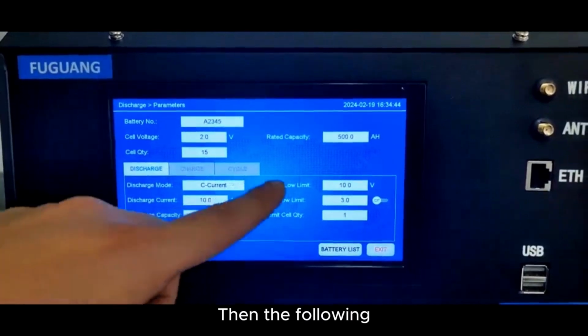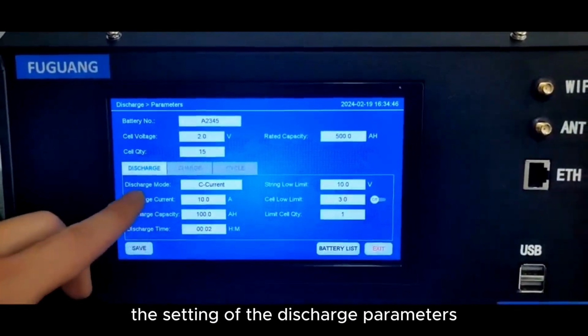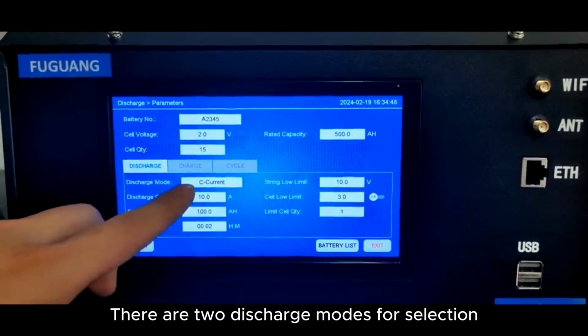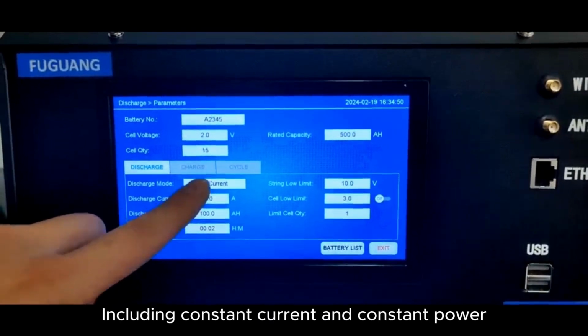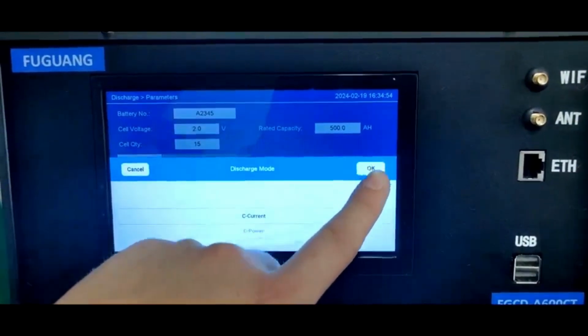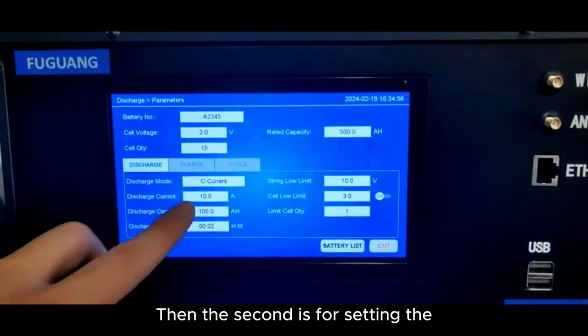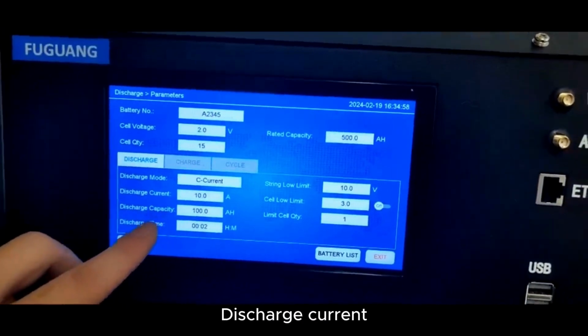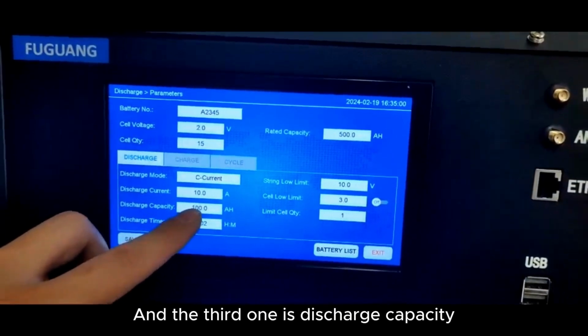Then the following is the setting of the discharge parameters. There are 2 discharge modes for selection, including constant current and constant power. Now I will choose the constant current mode and click OK. Then the second is for setting the discharge current, and the third one is discharge capacity.